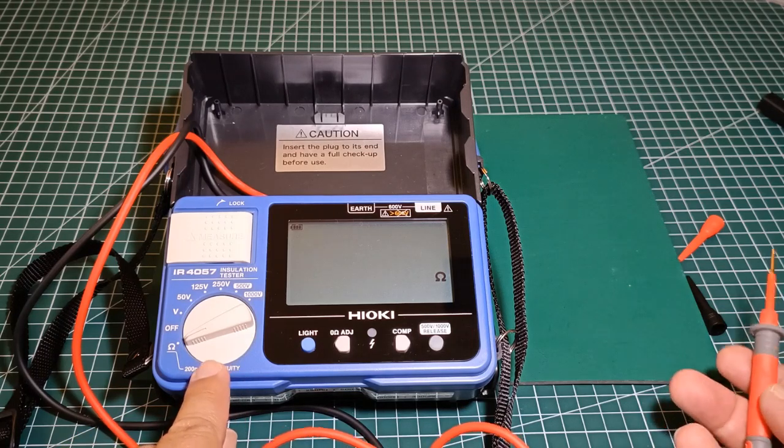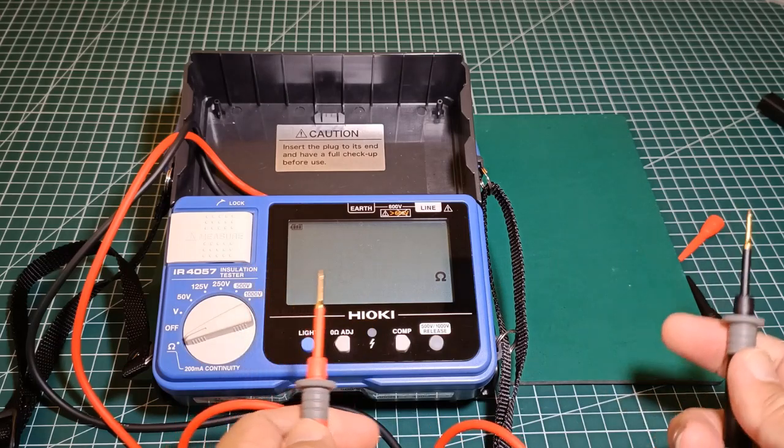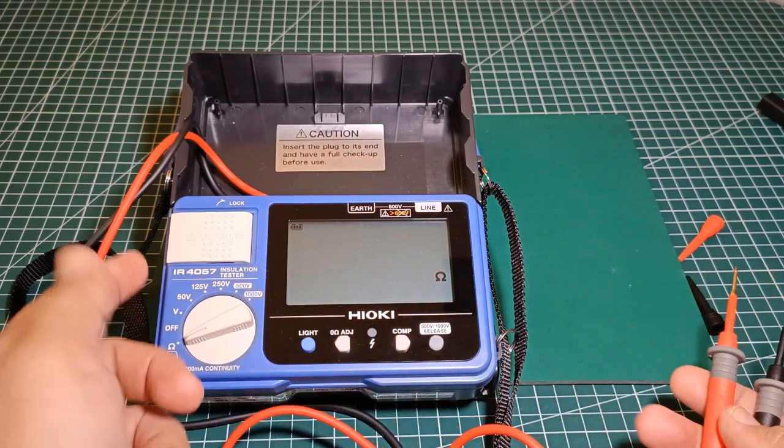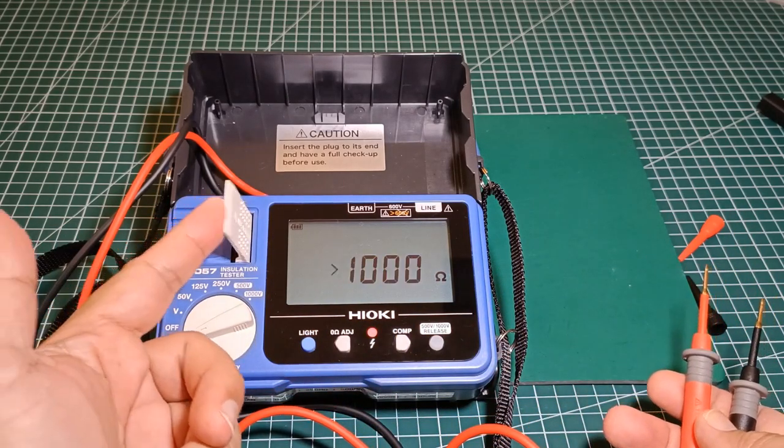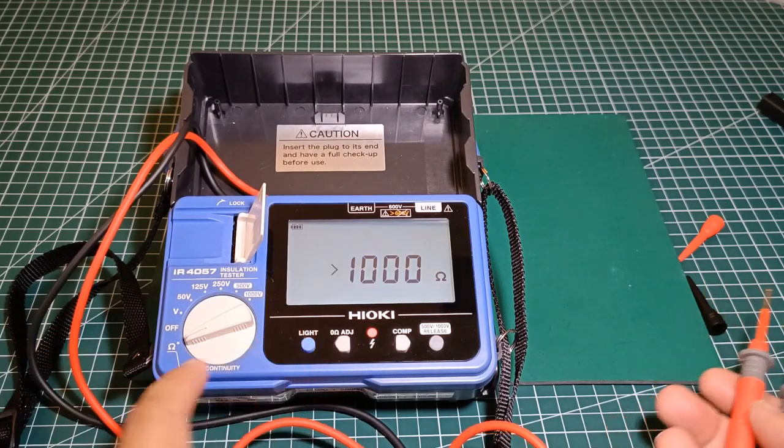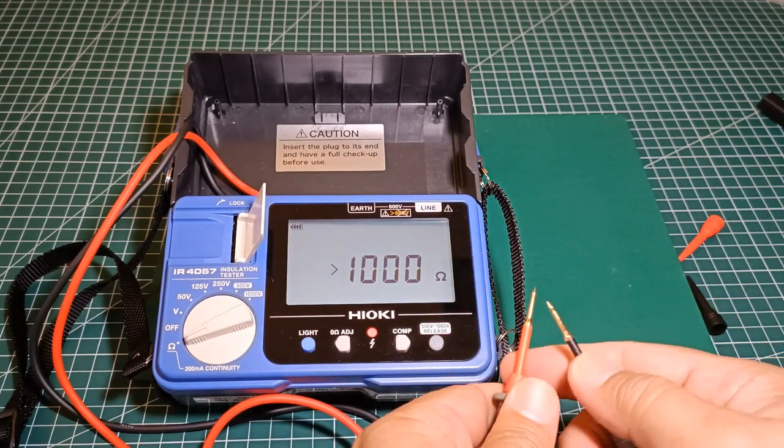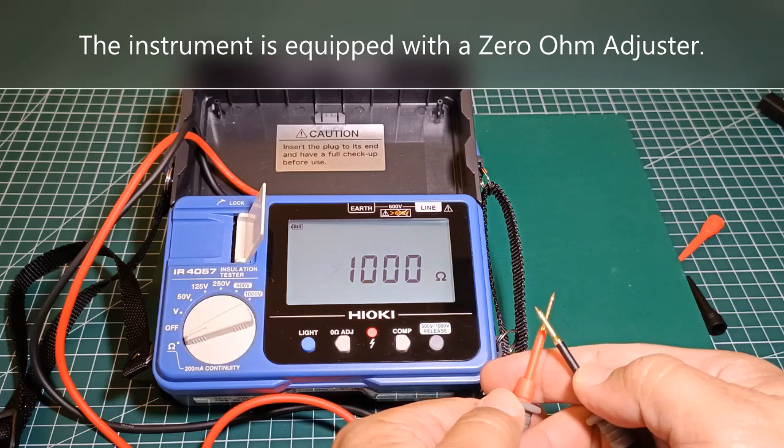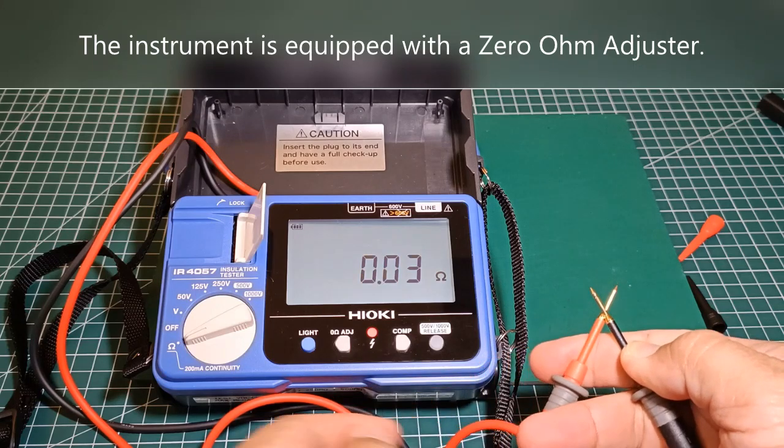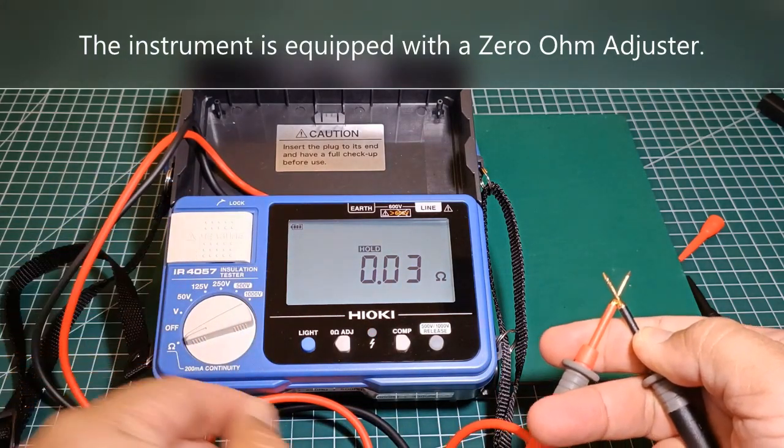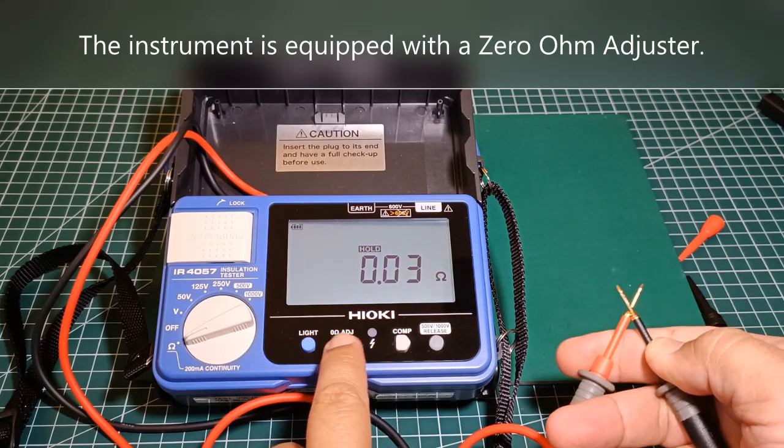To use this function to measure low resistance values, flip open the measure key, connect the tips of the test leads together, flip back the measure key, and press the zero ohm adjuster.